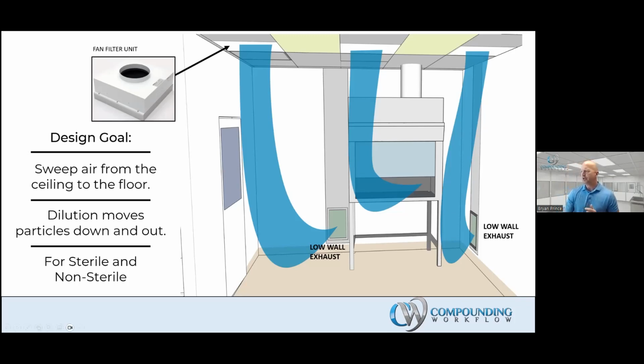There's a carve-out that says if you put the return on the ceiling, you've got to prove it with a smoke study. And let me be the first to tell you, you'll never, ever prove a smoke study if your returns are located on the ceiling. So this design goal of sweeping air is specifically called out in 797.